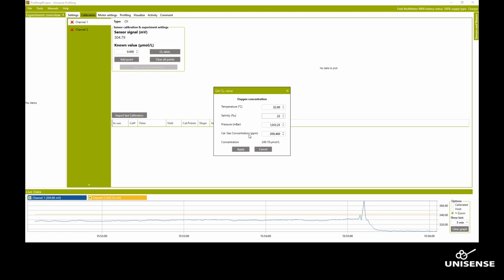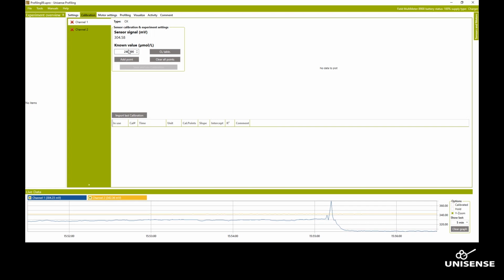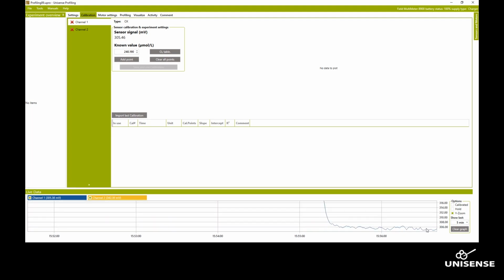And then you can enter the gas concentration in the calibration gas you're using. In this case, it is atmospheric air, and that is 20.946% oxygen. So this is pre-filled, so I will just accept that. And then the concentration in the water will be 240.19 micromoles per liter. Now I click apply, and then this value is transferred to here. In the meantime, this has stabilized. Oops, sorry. So you can see it's now stabilized, so I'll accept this.